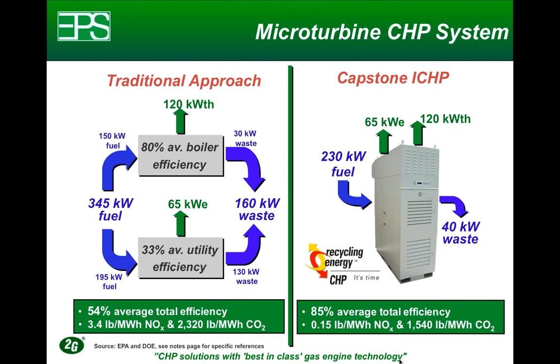Like the reciprocating engine, you can do cogeneration with the microturbine. Looking at the right part of this slide, the bottom section here is the microturbine. Because there are no oil and cooling circuits on the microturbine, all the heat is present in the exhaust. So that is also where the heat recovery takes place. With a unit like this, the exhaust outlet is at the top. This is where we can mount an exhaust heat recovery unit and have a fully integrated module. Gas is supplied to the unit, electricity is provided, and heat in the form of hot water comes from the exhaust. Again, we can achieve about 85% total system efficiency with those microturbines.